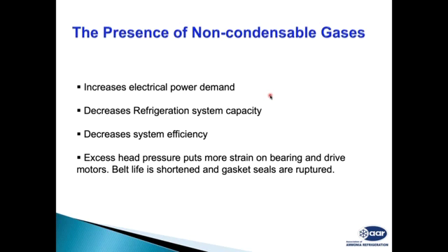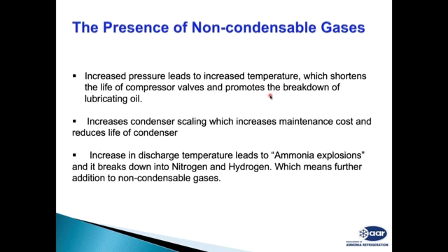Then also, as the air pressure increases, the pressure in the system increases, and excess pressure leads to bearing and drive motors heating. It also shortens the belt life. Gasket failures are regular with the compressor. Then the increase in pressure also increases the temperature, which shortens the life of the compressor valves, and the breakdown of the lubricant oil in the compressor also happens.